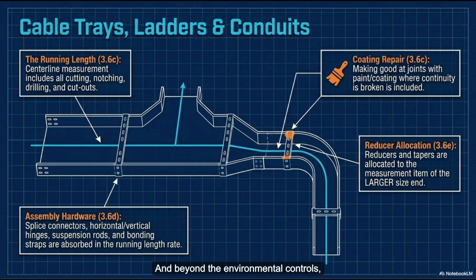Exactly. And beyond the environmental controls, the mechanical requirements are dense. If an instrument comes with delicate capillary tubes, the contractor must handle, assemble, and secure those tubes without kinking them. And carefully coil and secure any surplus perfectly, I assume. Yep. Drilling backplates and fabricating custom steel work for mounting these instruments is also deemed to be included in the single unit rate. This feels like pulling a power cable is like plumbing a water main, but installing a vibration probe on a generator is like performing brain surgery. That's a great way to put it.